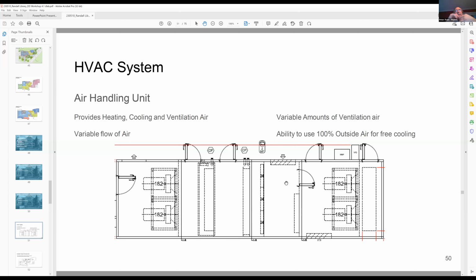The heart of the HVAC system is what's called an air handling unit. That unit is made up of several components: supply fans, heating and cooling coils, dampers which modulate the amount of outside air coming into the unit, and return or exhaust fans that take air from the building and recirculate it back through or exhaust that portion of the air.